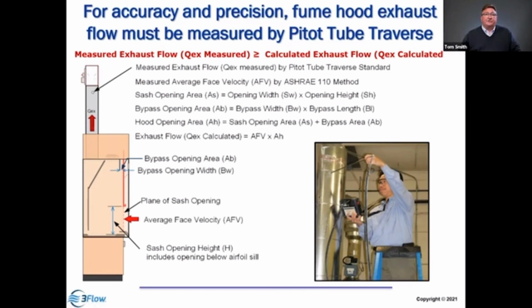The flow of the exhaust duct must always be greater than the flow through the sash opening. Okay? The reason I say that is because you're going to calculate the average. You use your average velocity multiplied by the area of the opening, and that equals your calculated exhaust flow. But that's the flow of this opening. It does not include the flow of bypass or any leaks in the hood.